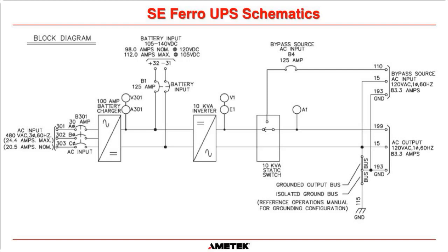Also, like I said, the battery is in parallel with the DC bus, and therefore the output of the rectifier charger and the battery are connected directly to the input of the inverter. And the inverter takes the DC and converts it into AC. So out here we have AC, and we have V1, which is a voltmeter on the output, and we have E1, which is a frequency meter on the output. Once again, both analog meters. And then we go into the static switch.